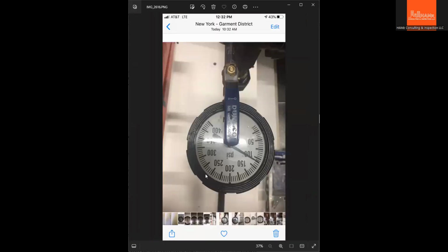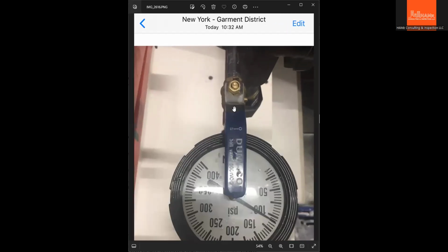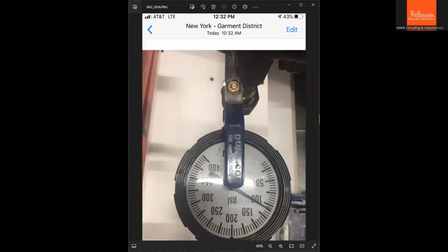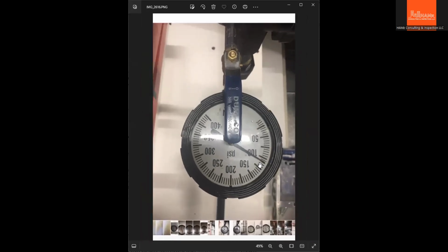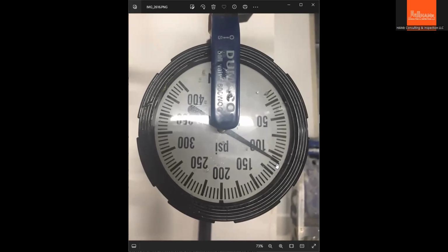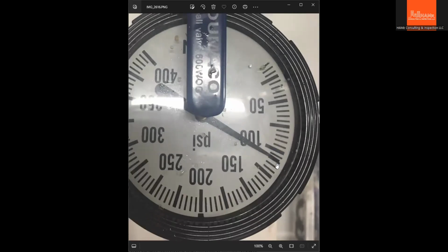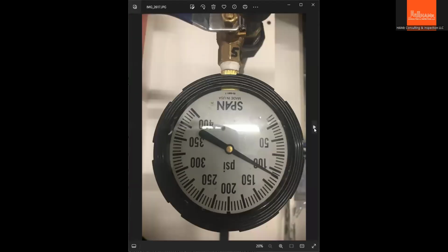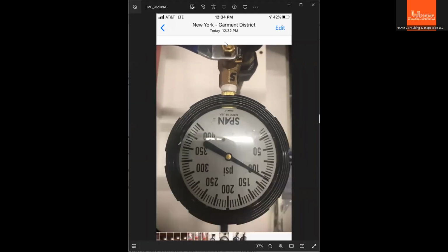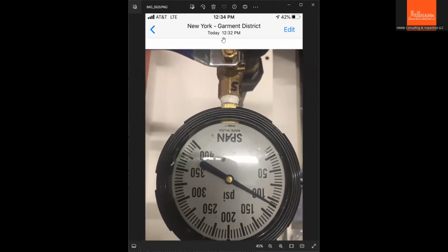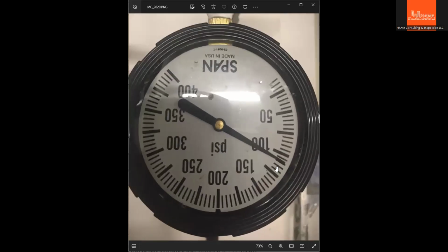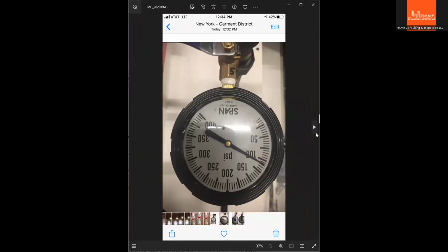steam piping test. So the original time that I have in here is 10:32, and then I have a screenshot at 12:32 after 2 hours. So the pressure is 108 or 109 psi, which is less than 110. And then the next photo is 12:32. So I took the photo again at 12:34, the screenshot is 12:32. So the pressure stays. It means the piping system is totally leak free. And if there are no visible leaks or drops at the joint connections, it means this piping system is free of leaks. So it's perfectly tight. So that's the low side of the steam piping.